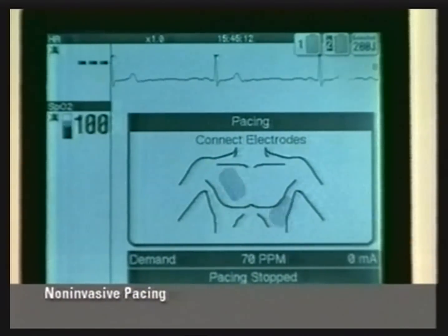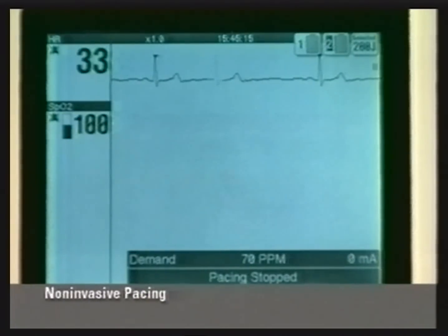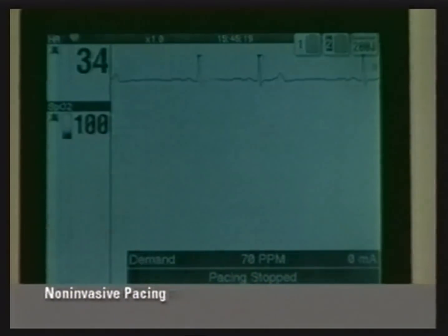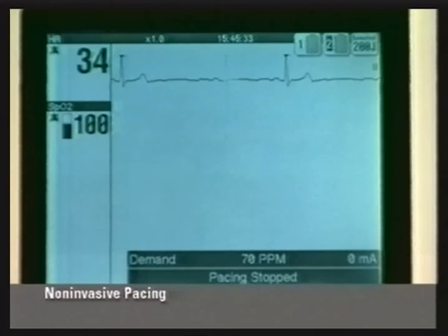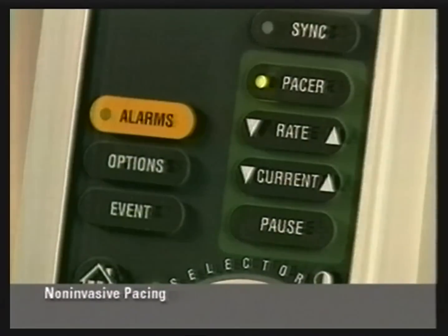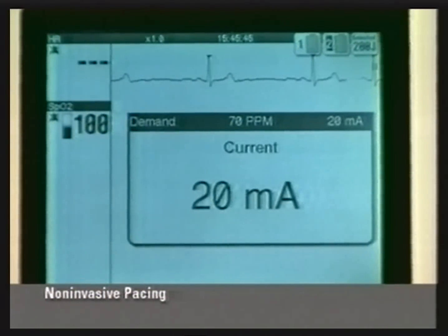After the electrodes are reconnected, the alarm silences, and the status message indicates pacer off and current is 0. If current is not increased within 20 seconds, the alarm repeats, reminding you to increase current. Increase current to resume pacing.